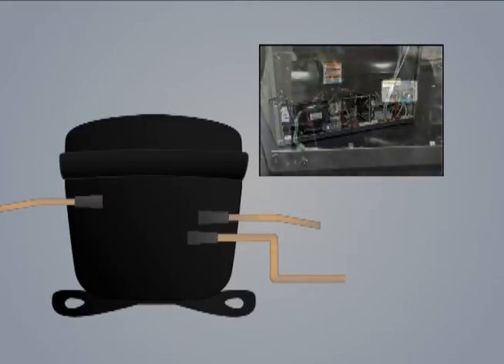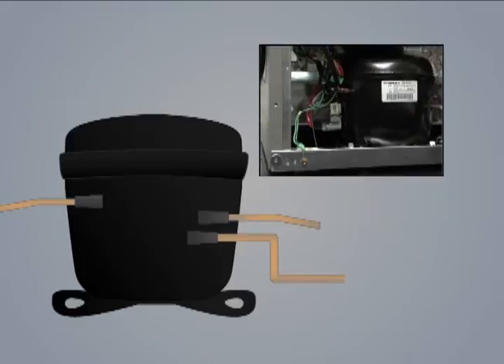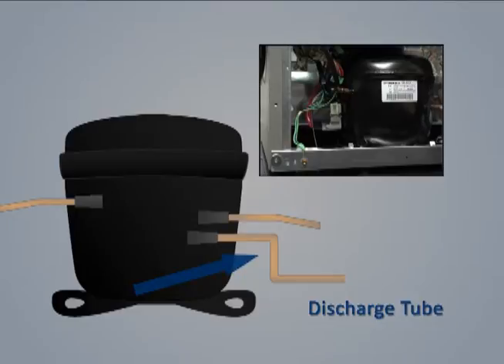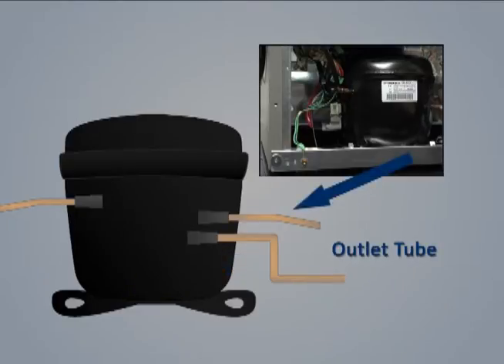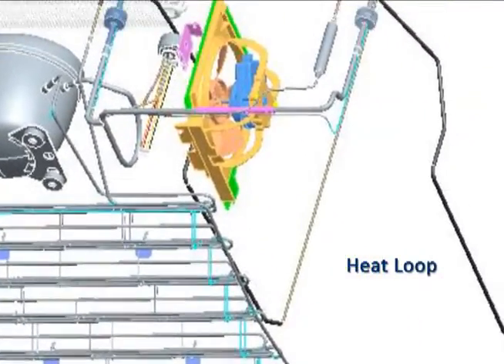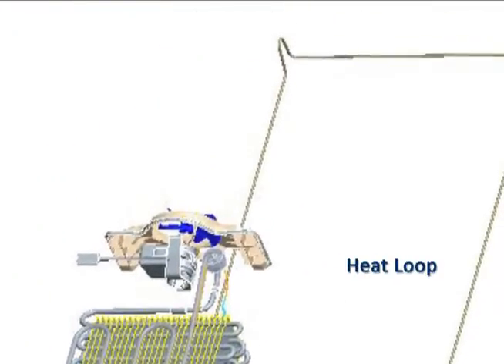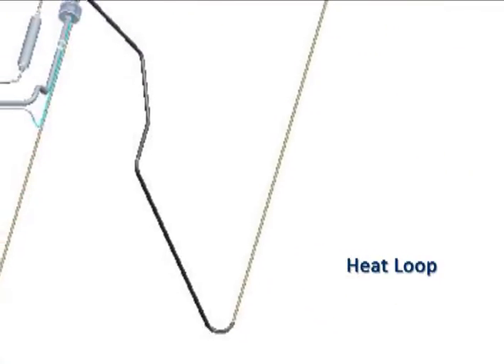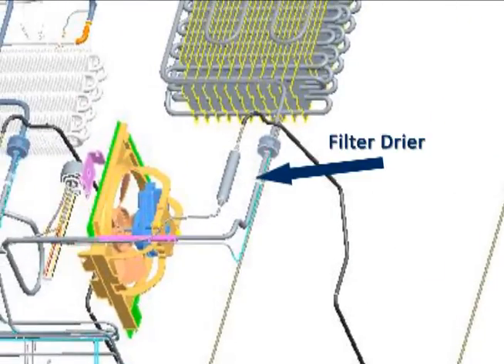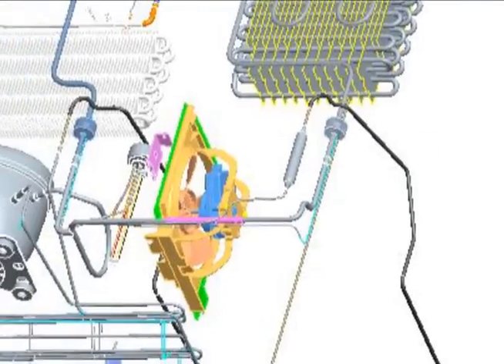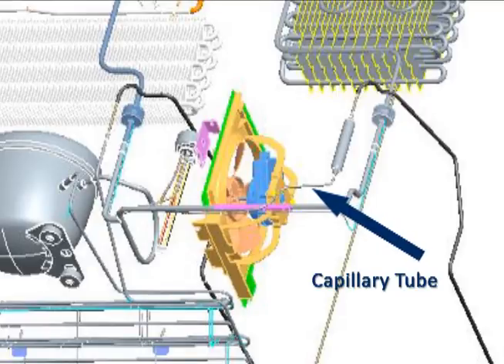Connecting the components. The compressor is the heart of the refrigeration system. The compressor consists of a reciprocal piston pump driven by a permanent split capacitor motor encased in a metal case. The discharge tube connects the compressor to the inlet of the condenser. The outlet of the condenser is connected to the inlet of the heat loop, also called the Yoder line. The heat loop tube is routed around the perimeter of the refrigerator cabinet door mating flange. The outlet of the heat loop is connected to the inlet of the filter dryer, which is designed to filter out debris and remove any moisture. The outlet of the dryer is a capillary tube, also called cap tube.